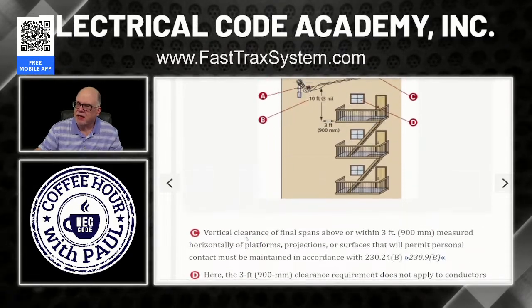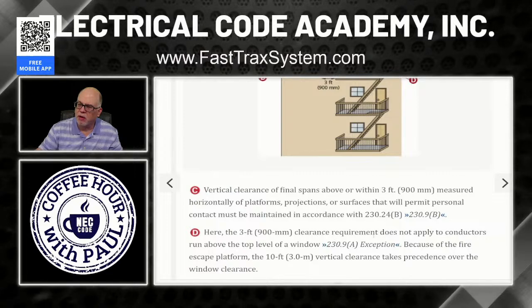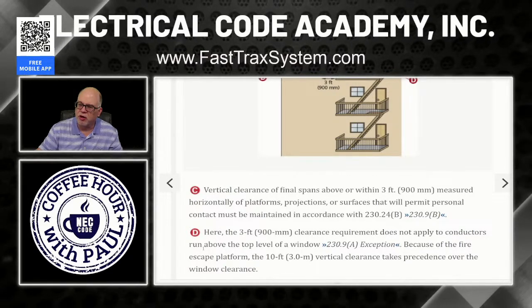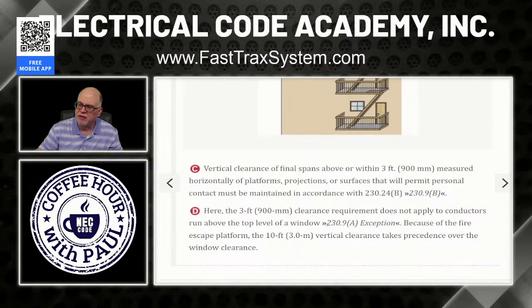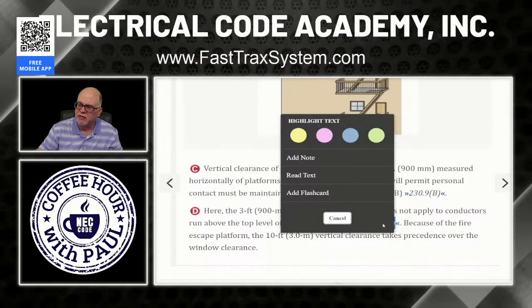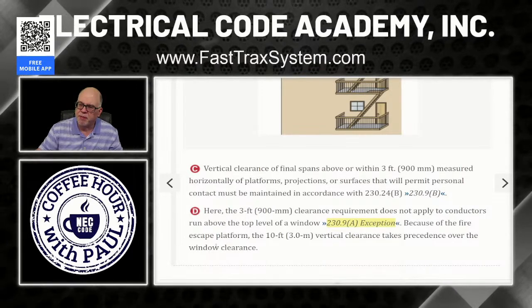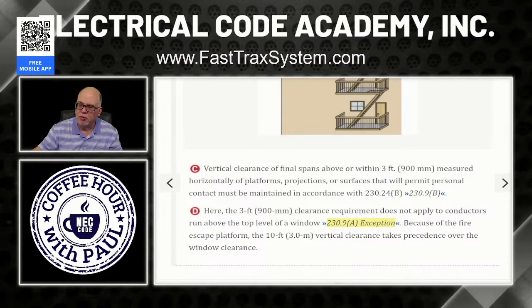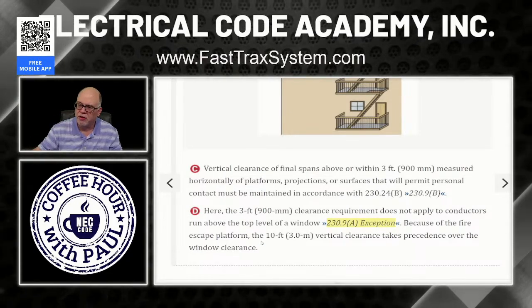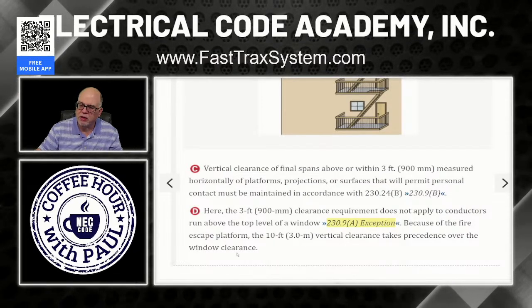And then D, right here, here's the window. It says here, the 3 foot clearance required does not apply to the conductors run above the top of the window. We saw that, okay? That was in the exception. It doesn't have to apply to the top of the window. Because the fire escape platform, because it is a platform, people stand on it, is it accessible to pedestrians? The 10 foot vertical clearance takes precedence over the window clearance.